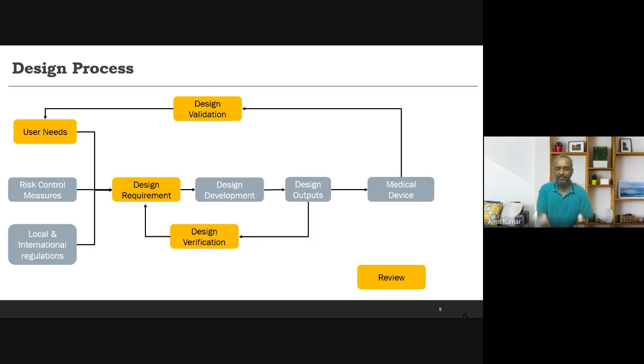And if it's the same requirement, but one country says I want to follow a stringent control, then that becomes the control point. So if FDA is asking for, let's say, a loose control, the EU is asking for a little tighter control, and SFDA is asking for a very tight control, the tightest becomes the specification, or the design requirement, for us. The reason is simple: if we are able to meet the tightest or most stringent requirement, then definitely we also meet the other requirements. So when we look at design requirements, it's a combination of all the regulations we are trying to comply with. Hope that answers the question. Yeah, thank you.